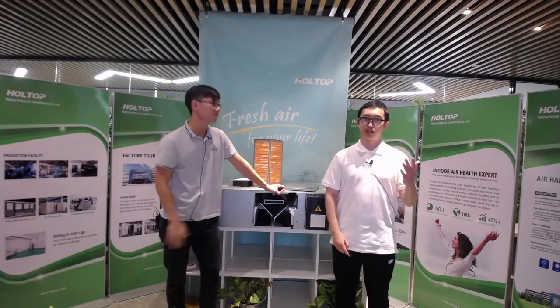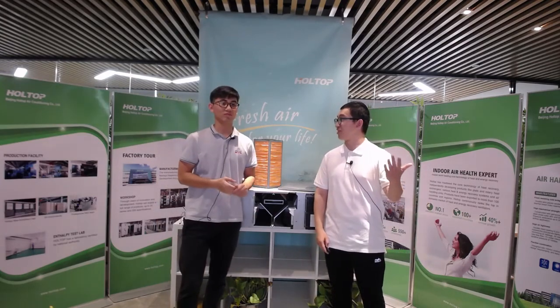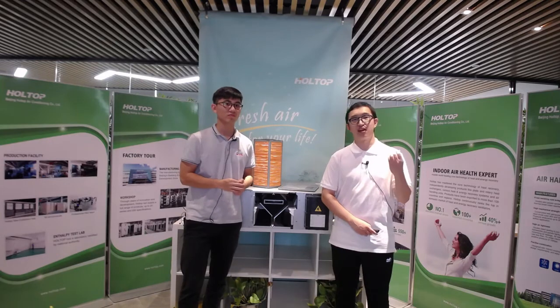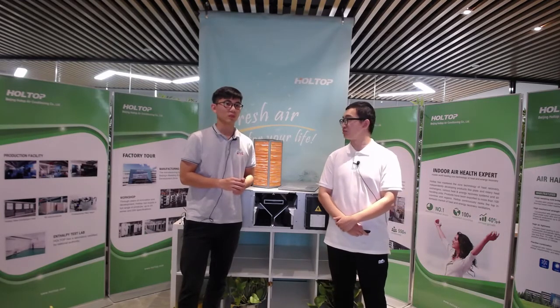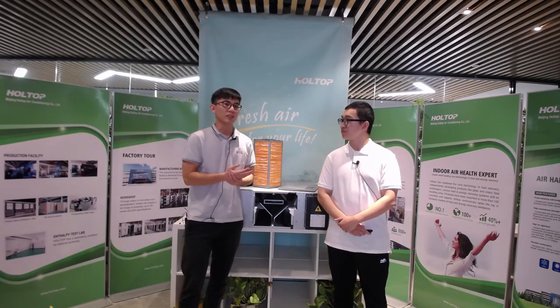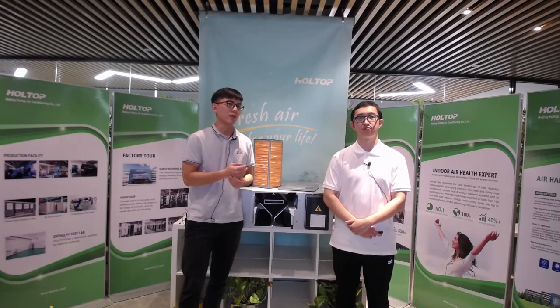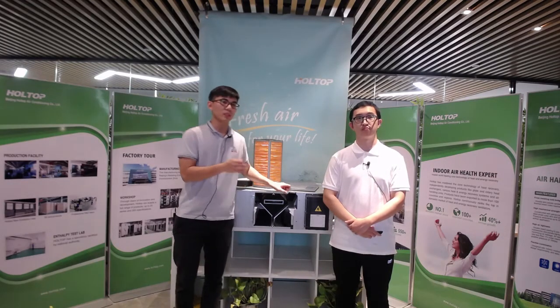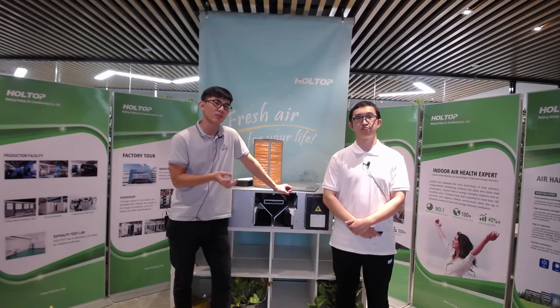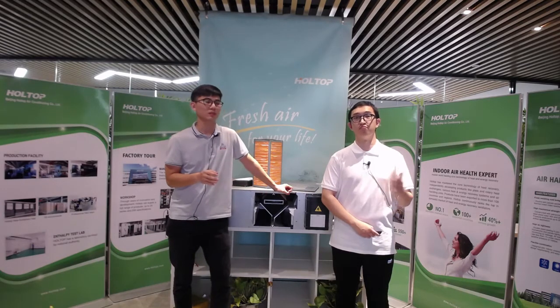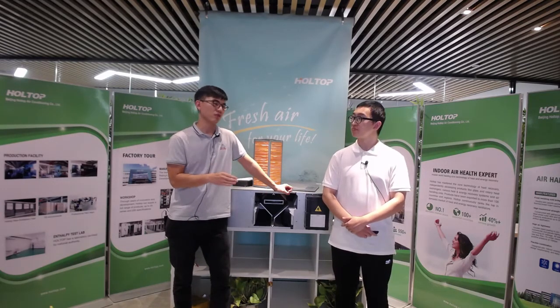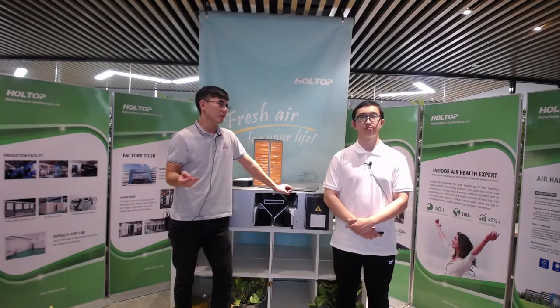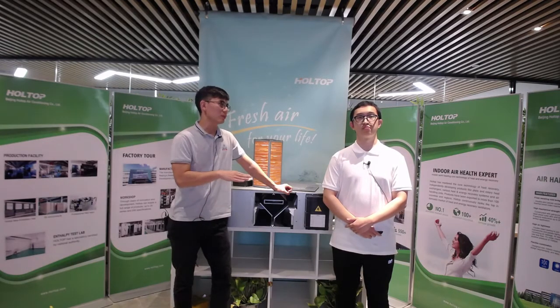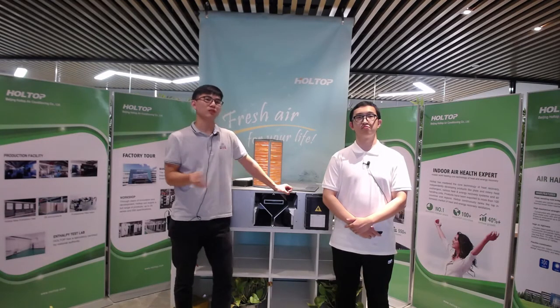And you mentioned a lot of fancy names up there. So what is night-free cooling and auto sensor control? Well, night-free cooling, you can also call it bypass. So during summer night, indoor heat can be discharged to outdoors, and cool air from outdoor will be introduced into the indoor directly without heat exchange, to save energy.